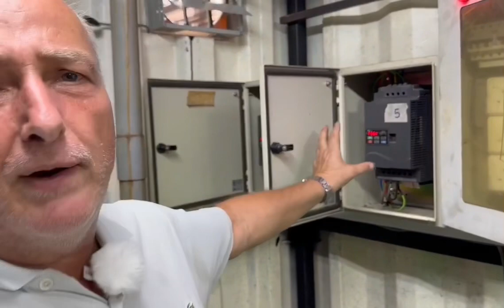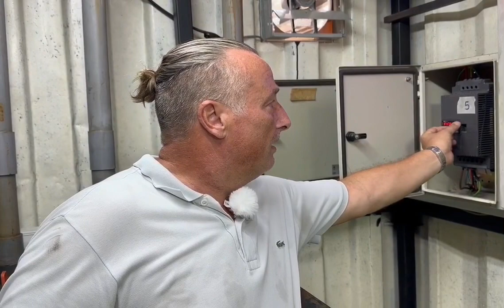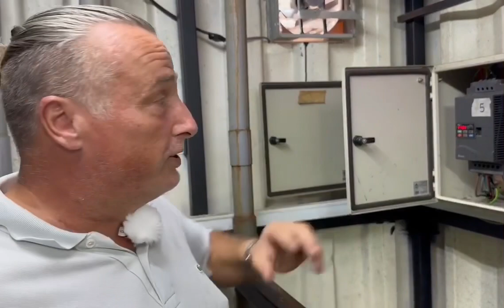We put up a frequency transformer. With this frequency transformer, I can regulate the hertz up and down, so I can increase or decrease the water flow by 16%. It's very simple, you can hear now I slow it down, and now I spin it up again. I can play with the hertz in my algorithm to control how much capacity I give out. Without this, we cannot increase anything. The frequency transformer is now at 49.4, close to what it should be.